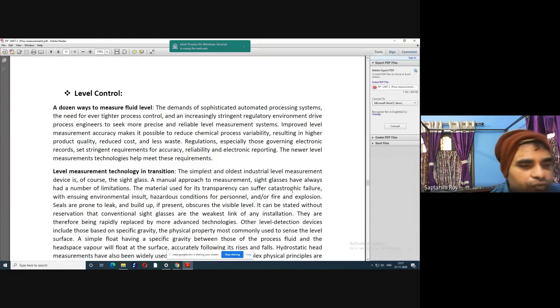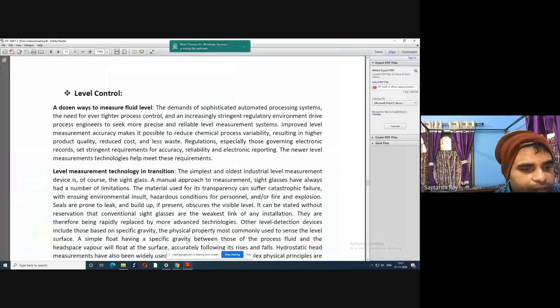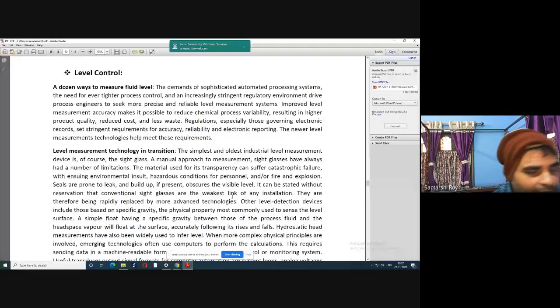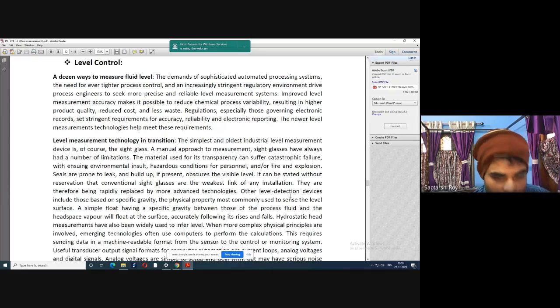It can be stated without reservation that conventional sight glasses are the weakest link of an installation. They are therefore being rapidly replaced by more advanced technologies. Other level detection devices include those based on specific gravity, a physical property most commonly used to sense the level surface. A simple float having a specific gravity between those of the process fluid and the headspace vapor will float at the surface, accurately following its rises and falls.